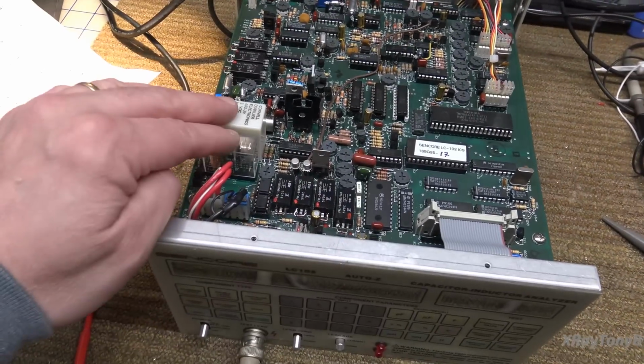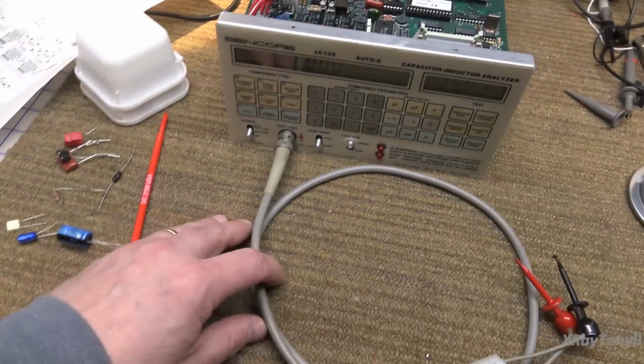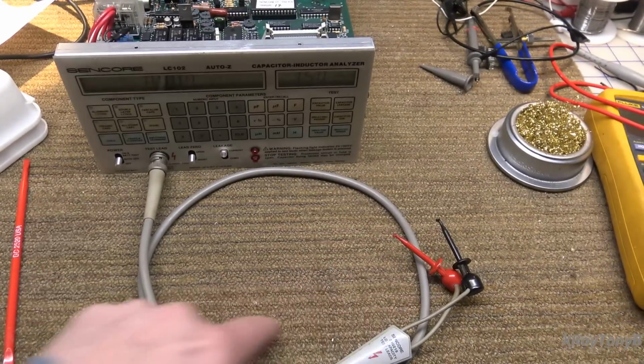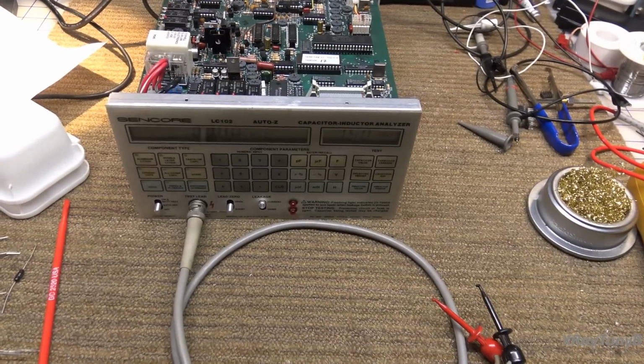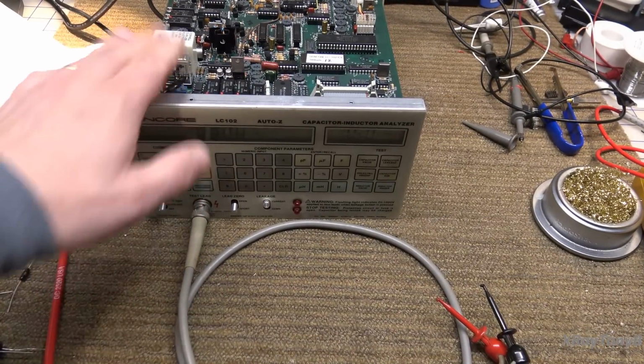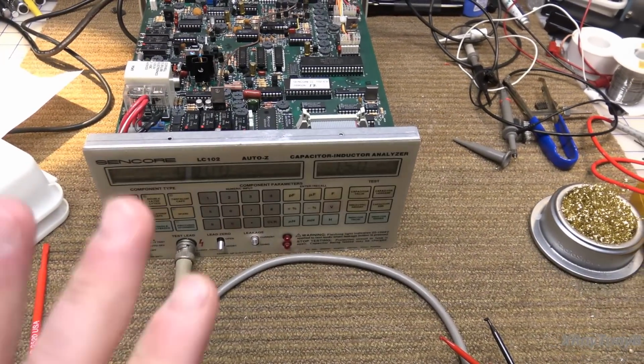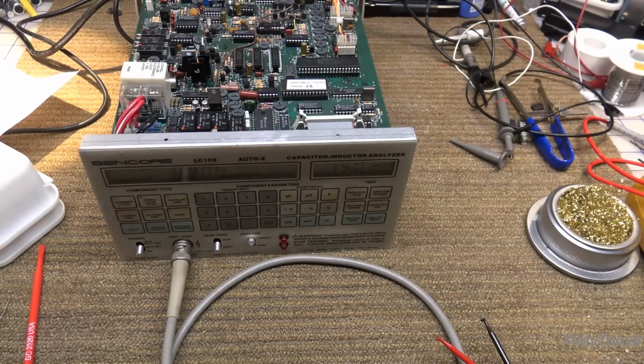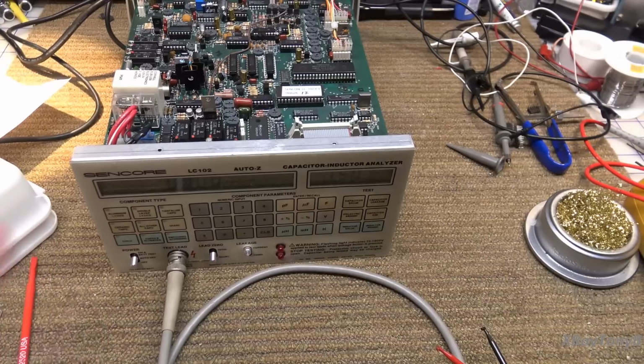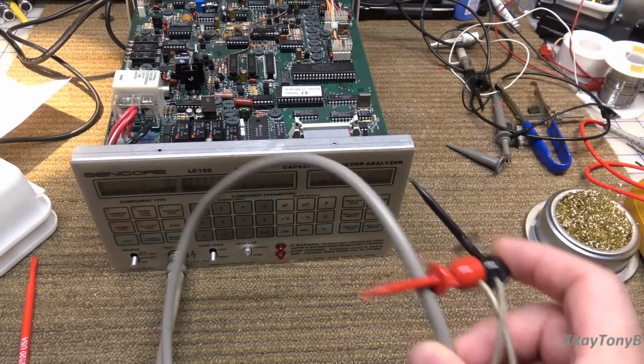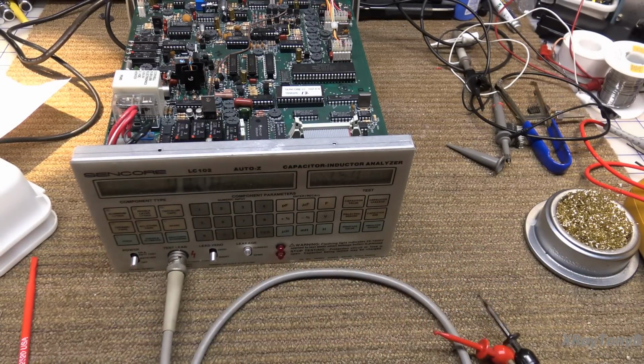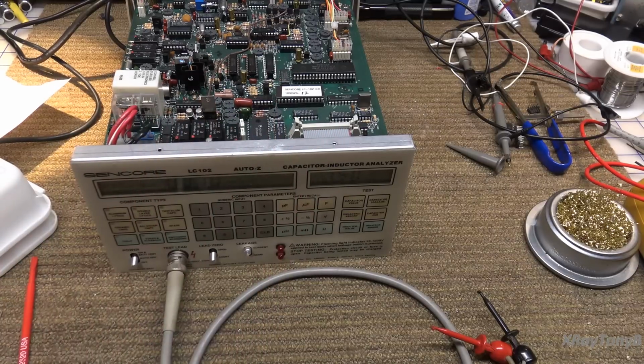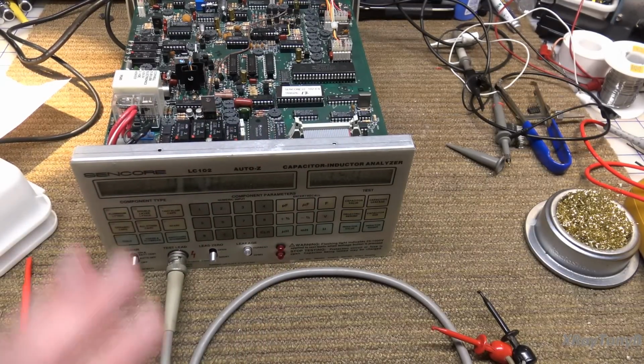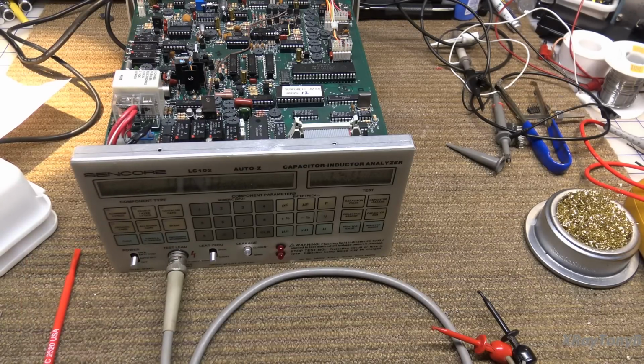All of the contacts are clean. I ohmed out these leads using my Kelvin leads, and the probe is fine. There's nothing wrong with it. I measured the test leads, all of the connections, they're all good. But that error 4 is still saying that the sense circuit is sensing that when we do the shorts test, or the short calibration, short leads for the zeroing, it's still out of range, and we have to figure that out. And that's kind of where I am with it right now.